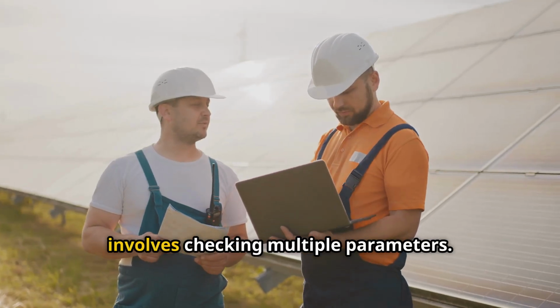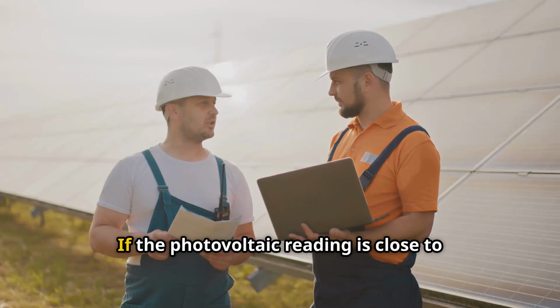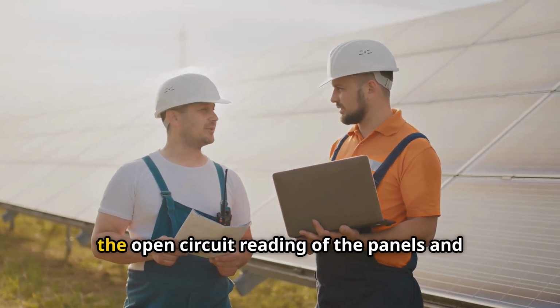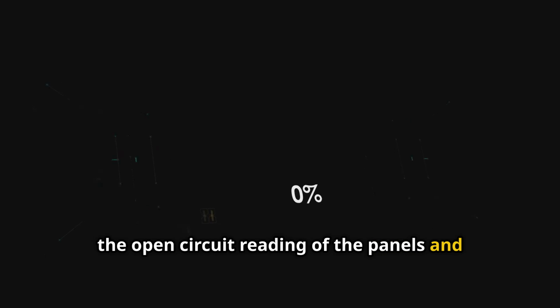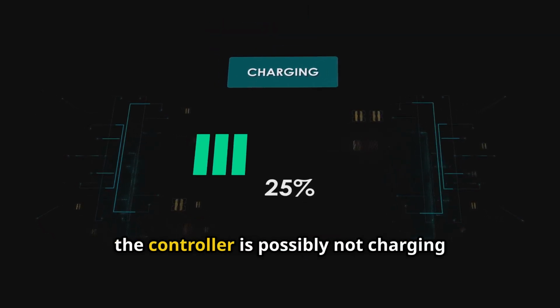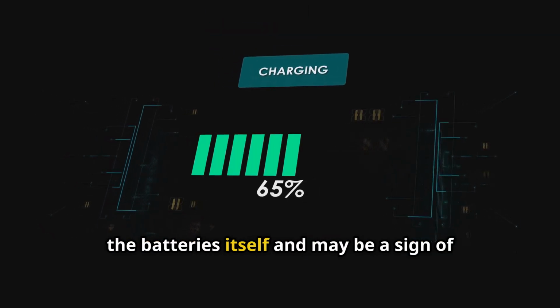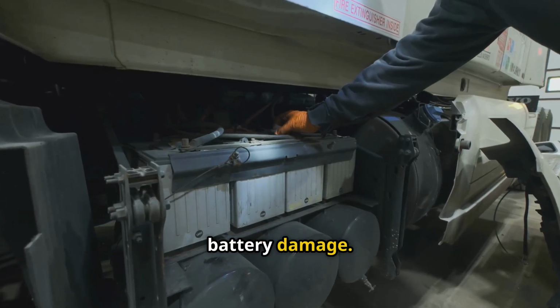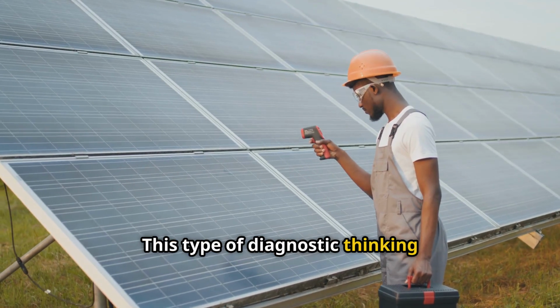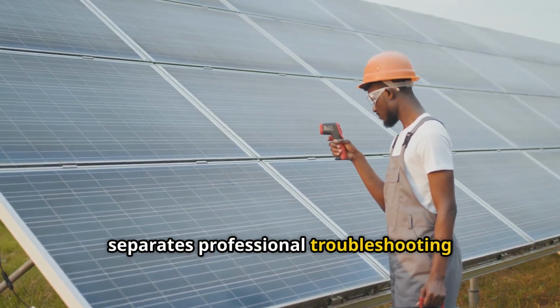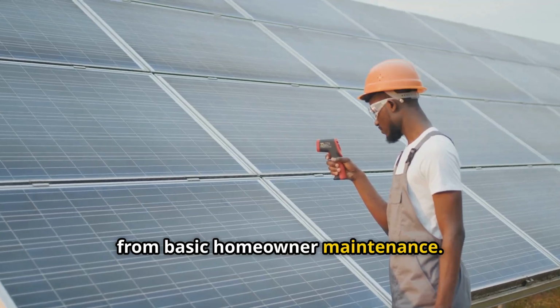Advanced inverter troubleshooting involves checking multiple parameters. If the photovoltaic reading is close to the open circuit reading of the panels, and the battery reading is low, the controller is possibly not charging the batteries itself and may be a sign of battery damage. This type of diagnostic thinking separates professional troubleshooting from basic homeowner maintenance.